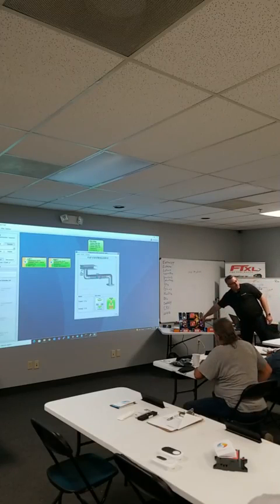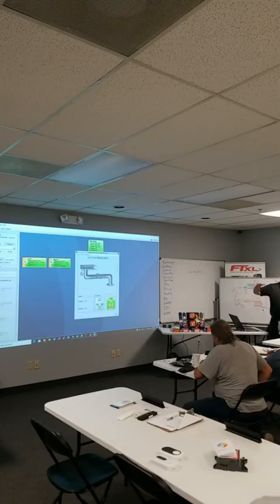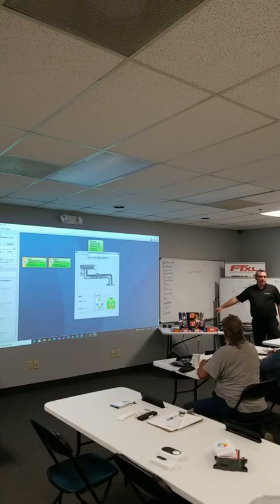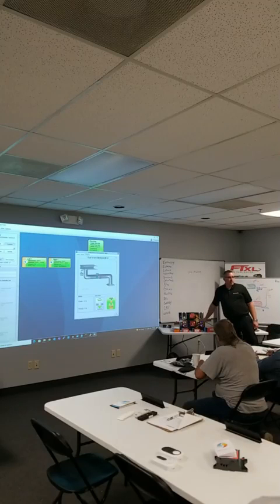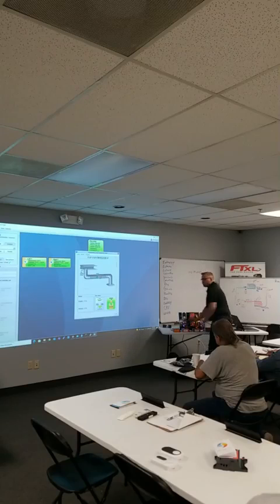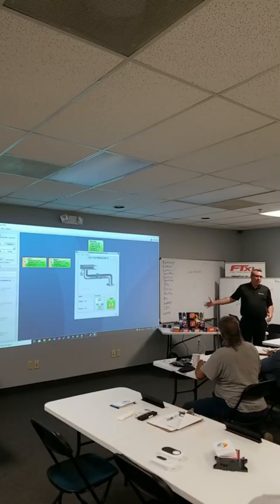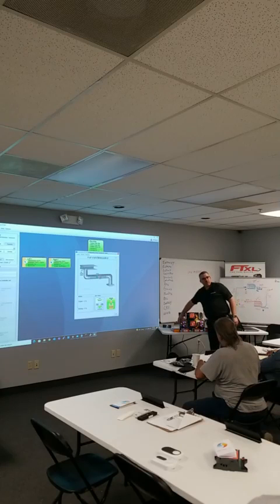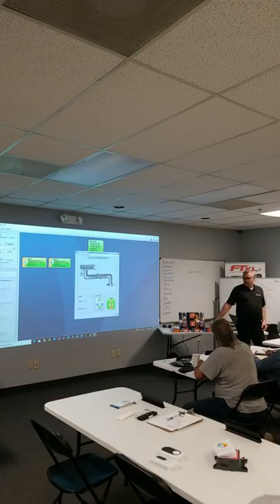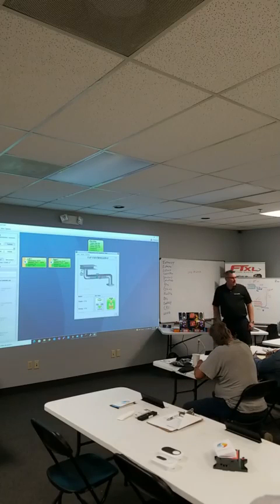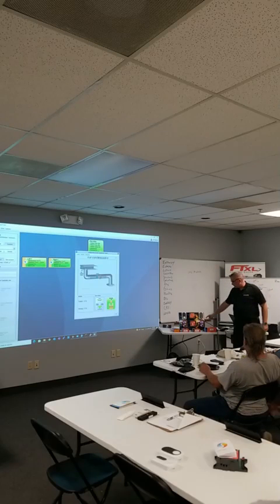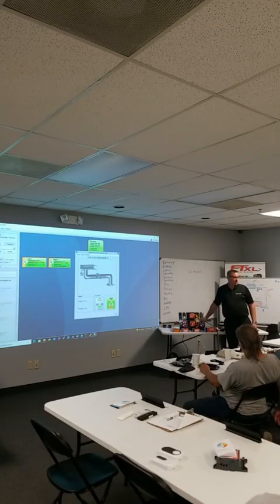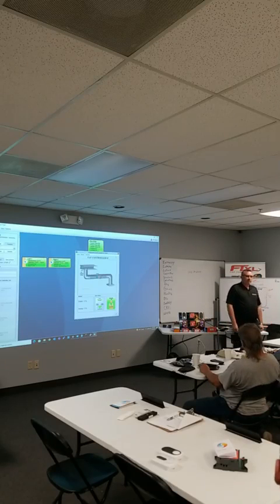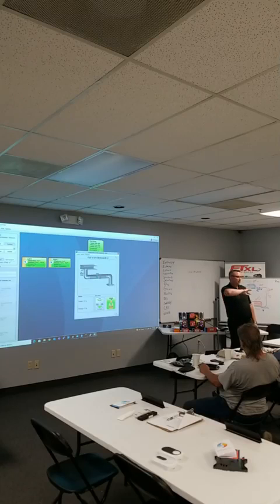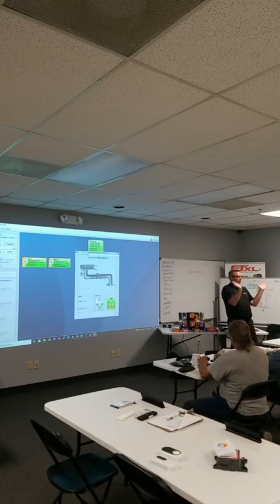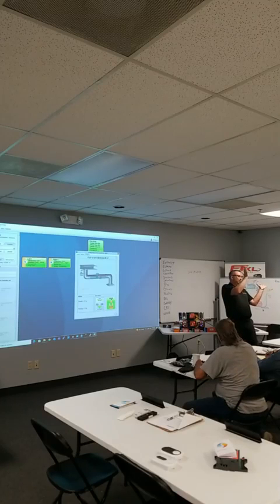So that's what the hard stops and the adaptation process are for, so that the controller knows, because it gives us a little eddy current feedback. On this, there is a clutch on the front of it. If you push the clutch and get that thing wide open, and then forget, the damper will be lost. Once you manually open the clutch, you need to power it down. Can't you just re-engage the clutch? Yes, but it doesn't know where it's at, because it goes through this process every time it starts. Every time the power goes out, or you unplug it, it drives open and drives closed, and it knows whether it's 90 degrees or 45 degrees, and it resets the scale.